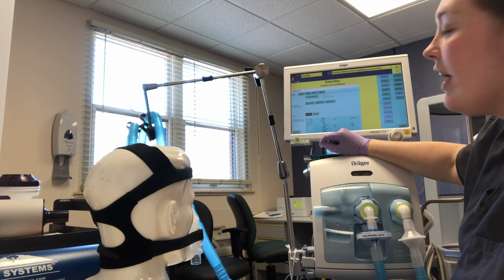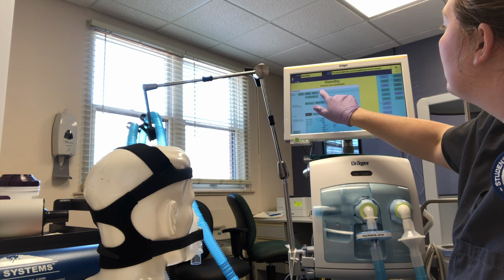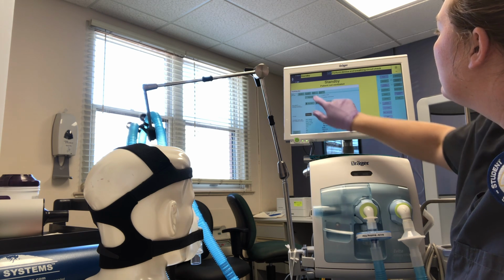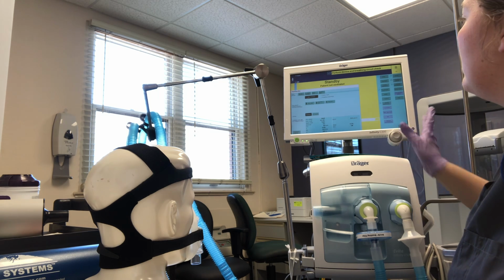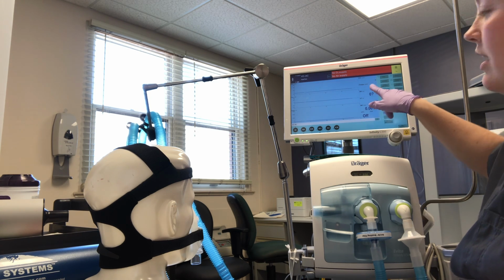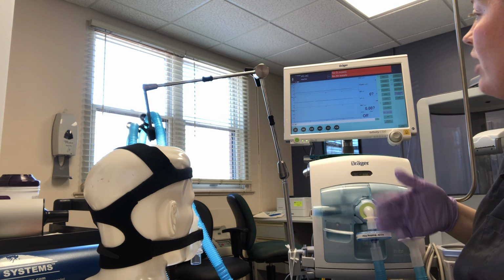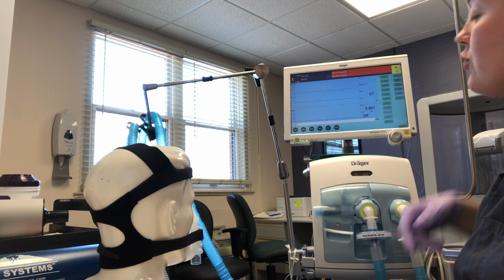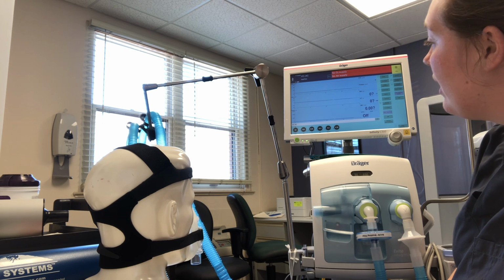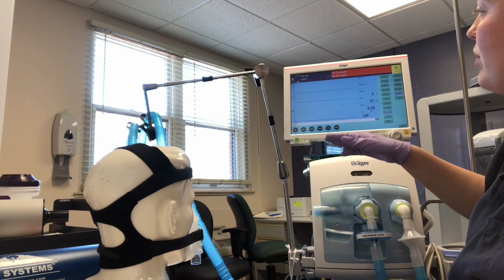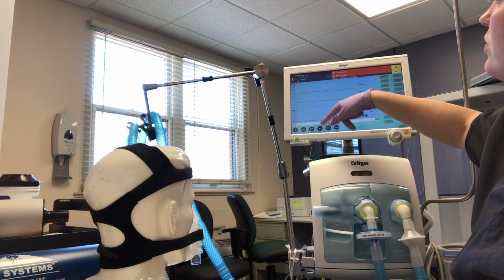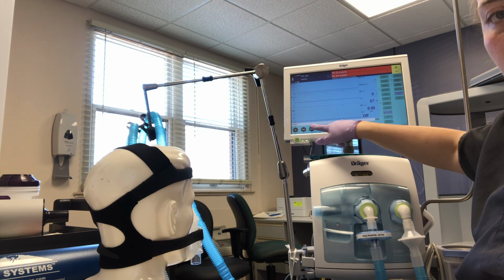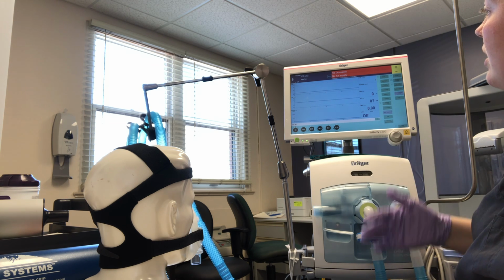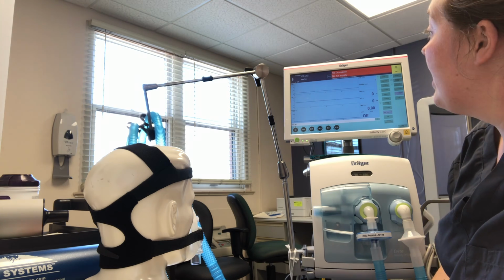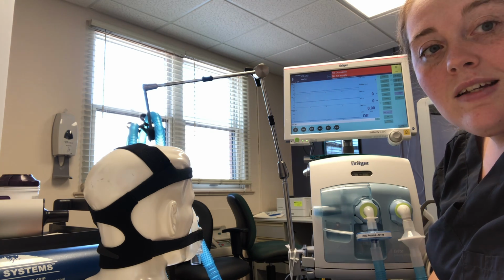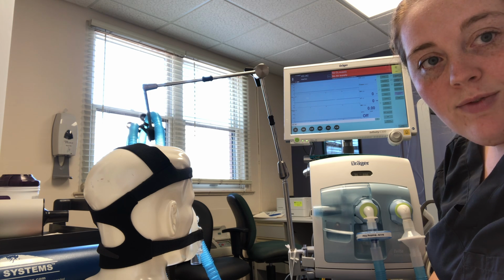It wants me to do a device check and a breathing circuit check. So you start now, my alarms are telling me that I don't have oxygen or air, which is true because I don't have it hooked up to oxygen or air, and I don't have this hooked up to my patient. But as you can see, it would show you your volume, your flows, and it has all of our settings down at the bottom. So besides the fact that we don't have the oxygen on and the air supply on, that is how you would set that up for ventilation with those settings for a patient.